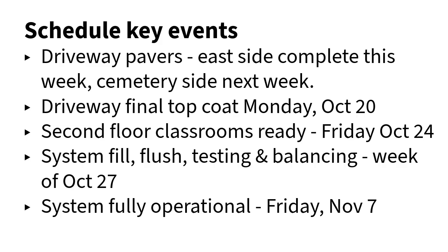This all has to be balanced too. You can't just run pipes to stuff and turn pumps on. You have to get the right amount of flow balanced across all 47 different radiator zones and up to the roof. That balancing will take place the week of October 27th. Then the week after, starting November 3rd, the building control systems vendor and others will come in and start bringing the system up, tuning it and adjusting the controls, so that by Friday, November 7th, the system should be fully operational. Cross your fingers.